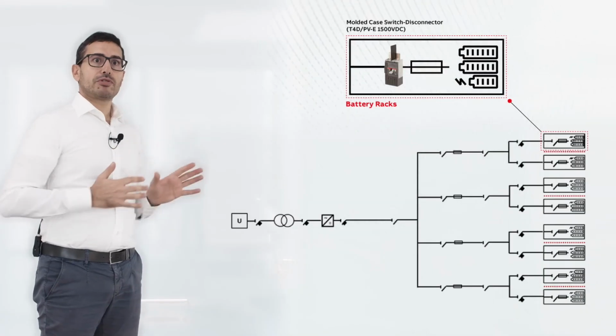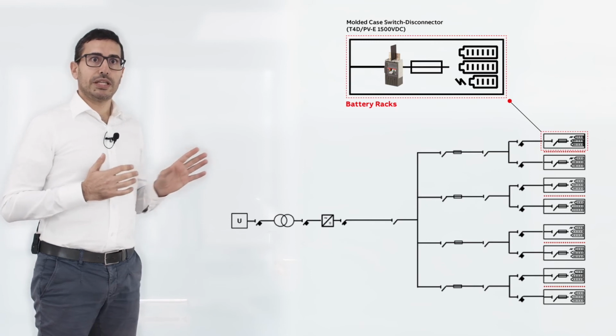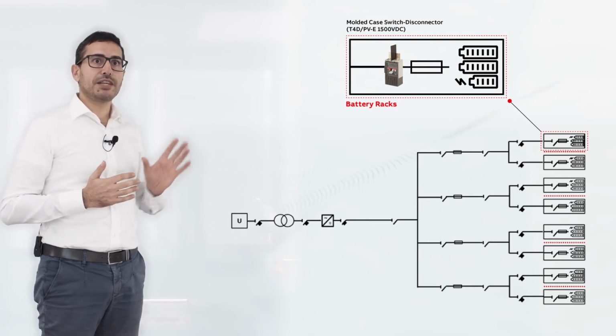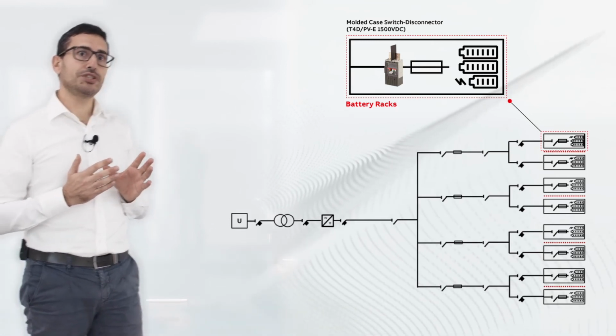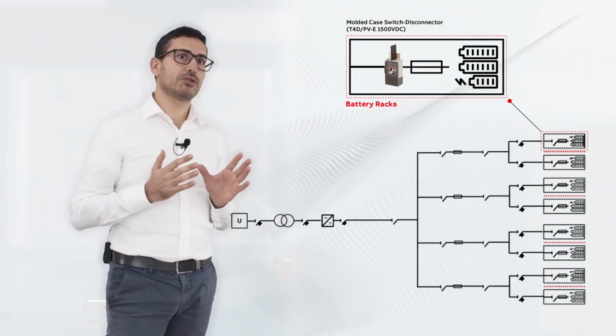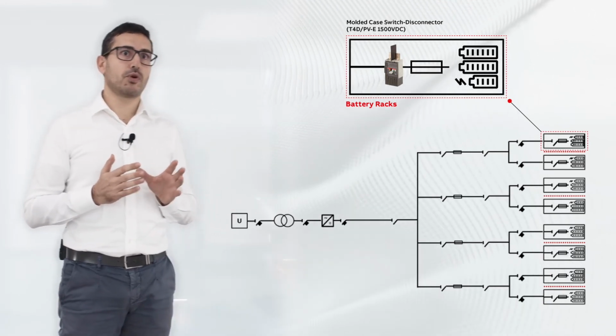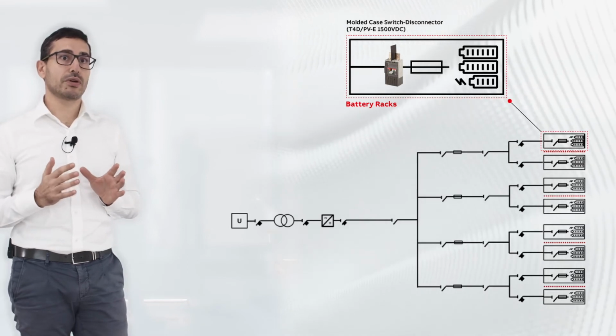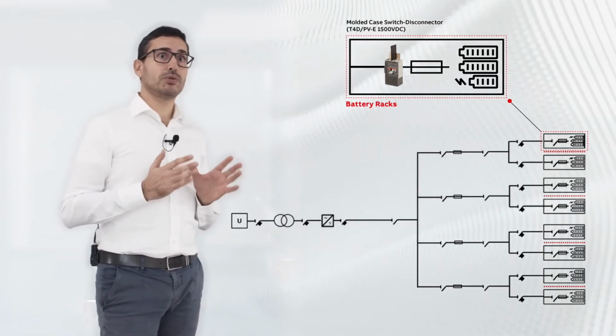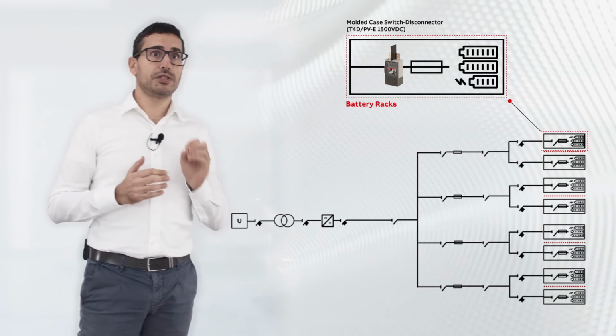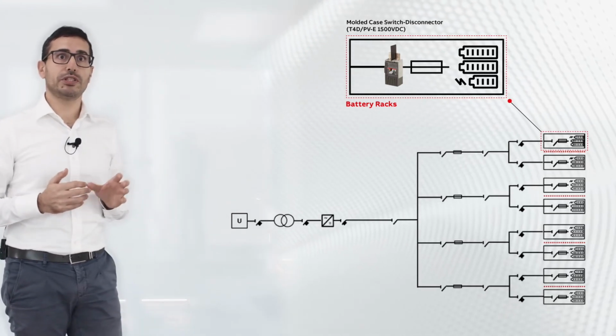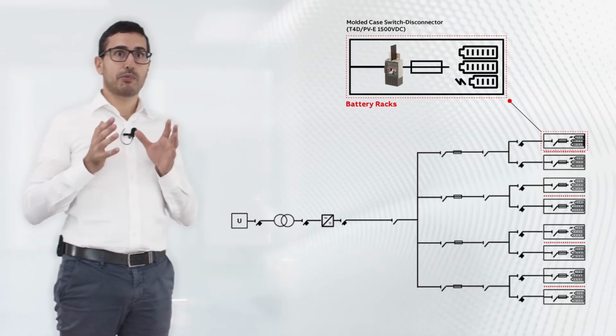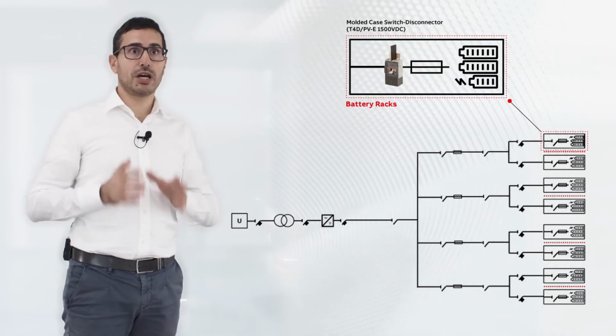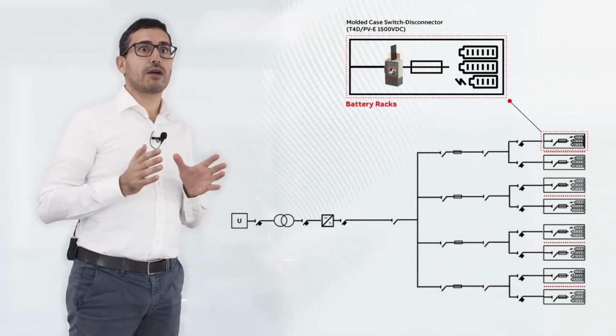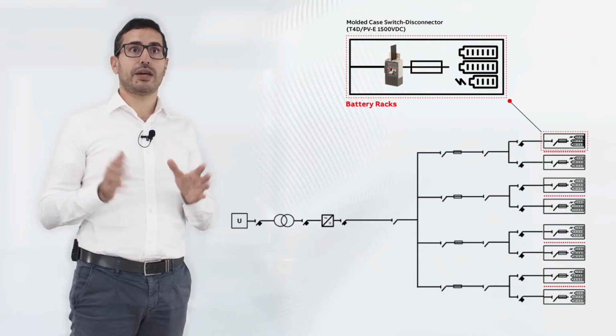Let's have a look at the protecting device we are installing in this application. As you may see, we are installing a switch disconnector. In particular, it's a T-Max T4 PV switch disconnector rated at 1500 volt DC. The switch disconnector, together with the fuse installed in the battery rack, is providing the appropriate level of protection against the overcurrent and short circuit within the battery rack.